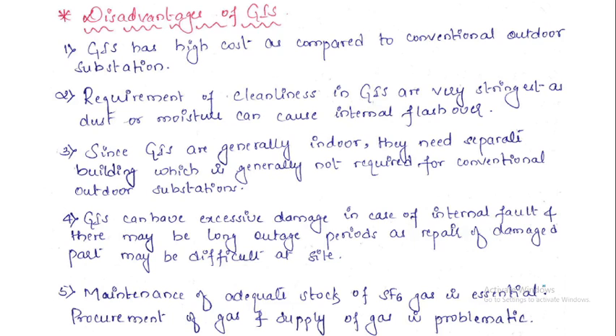Since GIS are generally indoor, they need a separate building, which is generally not required for a conventional outdoor substation. As GIS is indoor, it requires a specially designed building, which is not required otherwise.